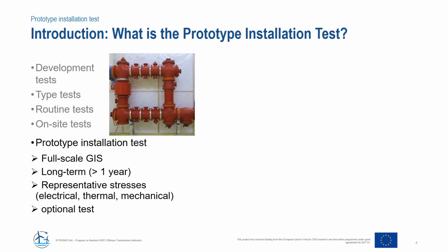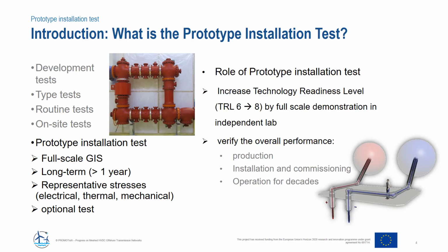This lasted for more than a year. And during this time, all the stresses are represented, including electrical, thermal, and mechanical stresses. There are also optional tests like partial discharge monitoring and diagnostics and checking, of course, and applying impulses and superimposed impulses as well. At the end of the prototype installation test, it's expected that the confidence of the user will boost significantly because it's under real operation condition, as I mentioned.